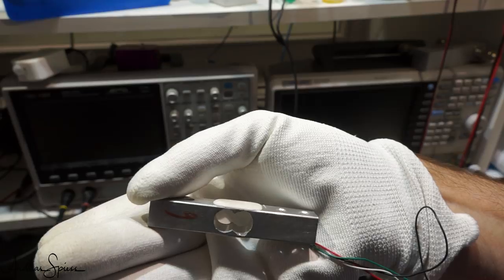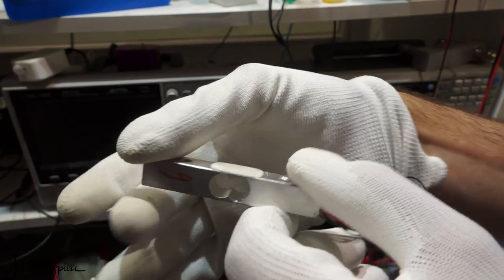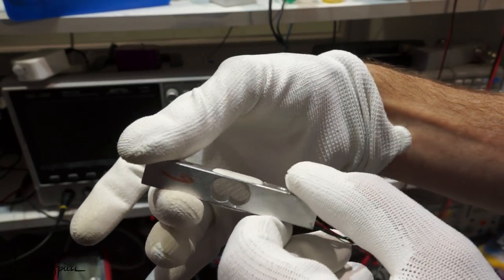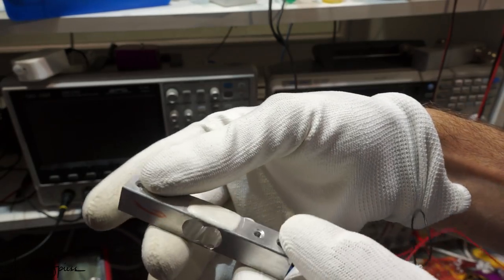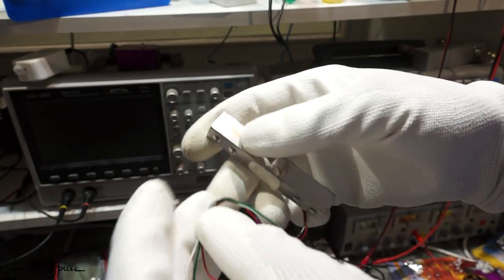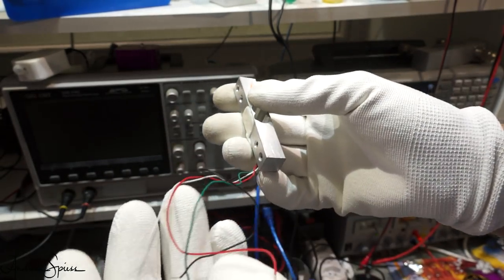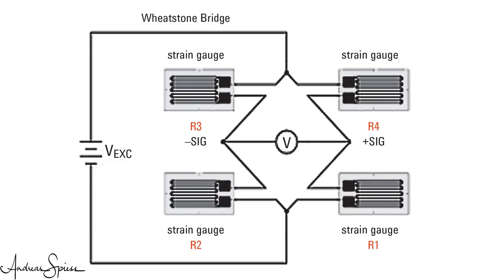And trick number three uses these two or four signals from the sensors and combine them in an interesting manner. It is called the Wheatstone Bridge, because Sir Charles Wheatstone popularized this concept already in the 19th century. Its main advantage is its ability to measure resistors extremely accurate, and it cancels temperature effects. This is exactly what we need here. So, we combine our two or four gauges into such a bridge.